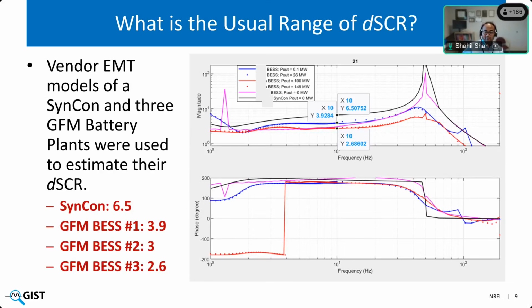What I talked about in the previous slide was just a single unit, either an inverter, wind turbine, or synchronous condenser. Here you are seeing the Q by V scan of an entire plant obtained from vendor-specific black box PSCAD models or EMT models. The black trace represents the response of a synchronous condenser. The three other lines, blue, purple, and red, are all grid forming BESS from three different vendors. The response of this Q by V transfer function is plotted on a per unit by per unit basis, to give an apples to apples comparison.